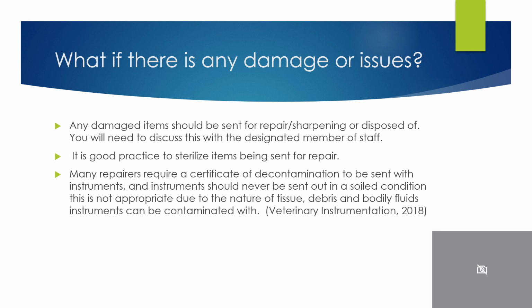You will need to discuss this with a designated member of staff, who is generally your senior or head nurse. It's good practice to sterilise items that are going to be sent for repair, and many repairers require a certificate of decontamination to be sent with instruments. Instruments should never be sent out in a soiled condition, and this is not appropriate due to the nature of tissue, debris and bodily fluids that they could be contaminated with.